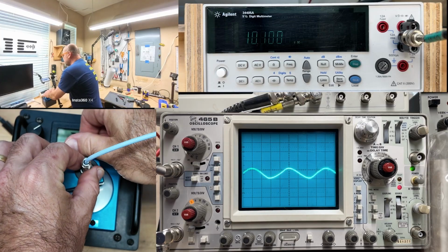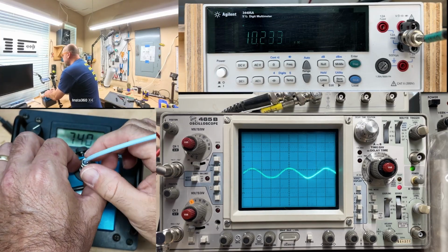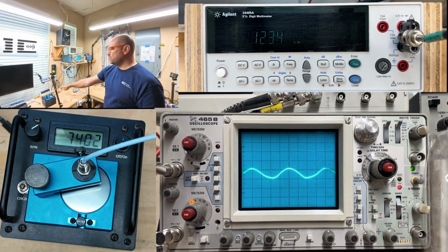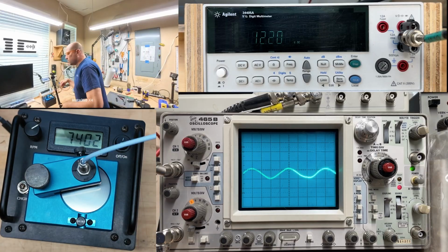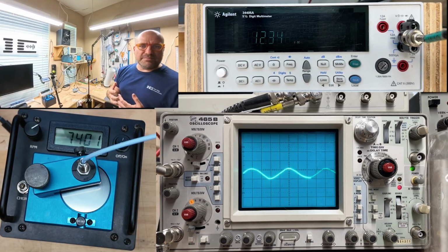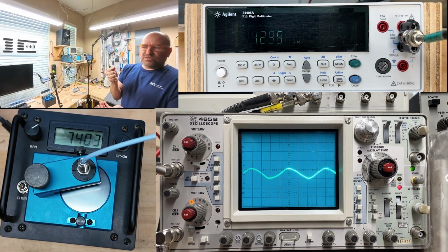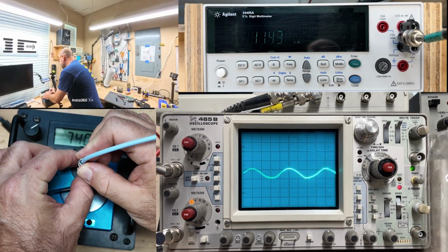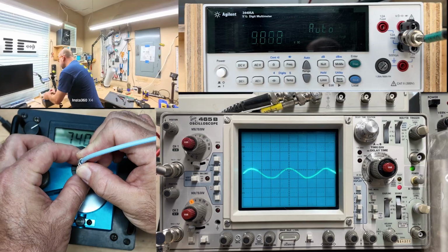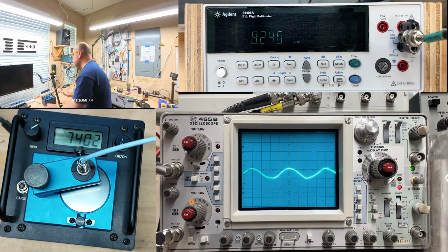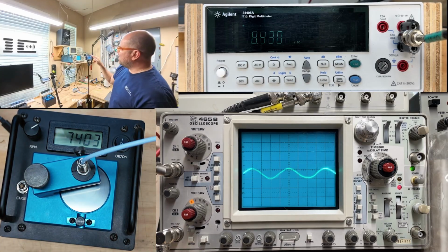I can move the probe. I'm going to move it a little higher. And you can see that I moved the probe to a gap voltage on the multimeter at around 12 volts. But my vibration signal is exactly the same. So I just separated the probe a little more, but I'm still looking at the same vibration amplitude as I was before. I can bring it back down. I'm going to bring it down to 8 volts. So my gap voltage is around 8 volts, and my vibration stays the same.